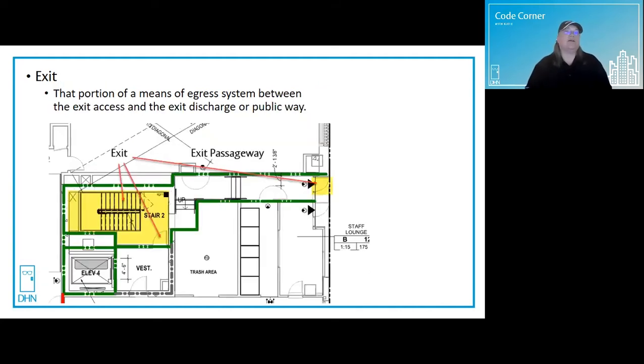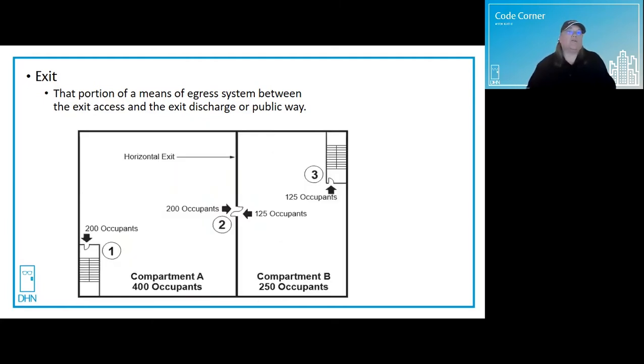And that is the exit, which is that portion of a means of egress between the exit access and the exit discharge or public way and safety. Exit components include exterior exit doors at the level of exit discharge, as well as interior exit stairways and ramps, exit passageways, exterior exit stairways and ramps, and horizontal exits.